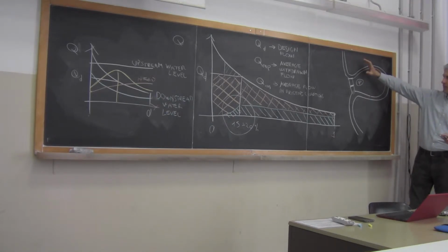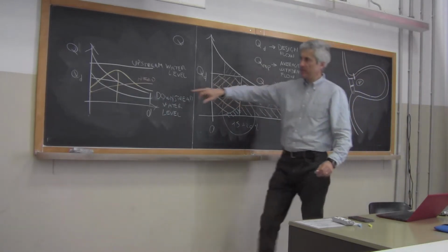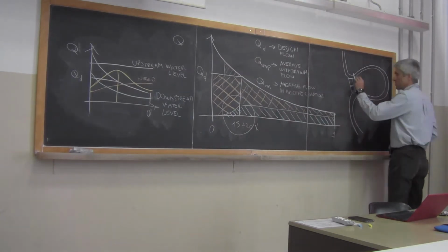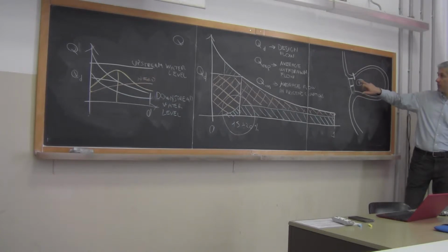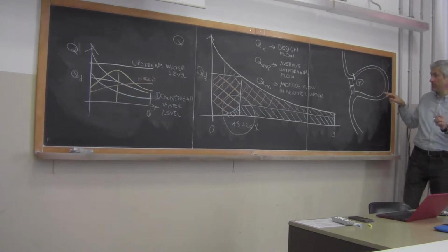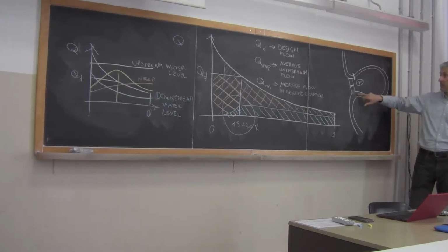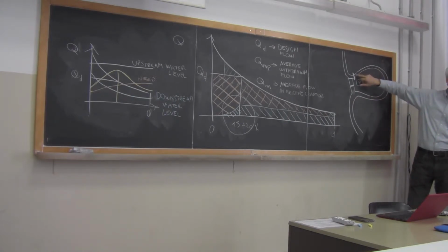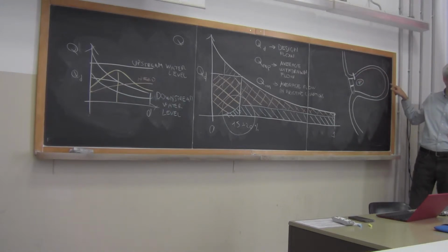So basically, there is also a gate here. When you have a flow that is lower than the design flow or up to the design flow, they close this gate and open this gate, and everything flows through the hydropower plant. They take care of monitoring the quality in the meander, because the meander doesn't get empty: here you have a water elevation in the river of about 15 meters, and the difference in elevation here is about a couple of meters. So water from here can flow back, and what you see at this gate is a difference in altitude between upstream and downstream, but it doesn't get empty. But the moral of the story is that you don't get any flow here. So they take care of monitoring the quality, and if they see that the quality is decreasing, they release some flow. So that gate is necessary for this to work?